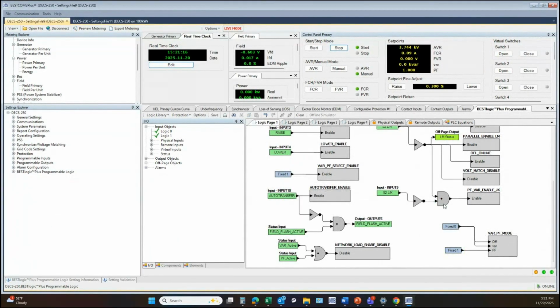So once I meet the conditions and enable this element, then it will, because of this logic, go into power factor control. You can set up inputs, or you can set up other logic to control whenever you want to go in the VAR, or you prefer to go in the power factor, or you prefer the off. And what the off actually is, it essentially is AVR droop, assuming you have droop enabled, and then it would resort to operating in droop while you're parallel to the utility grid.